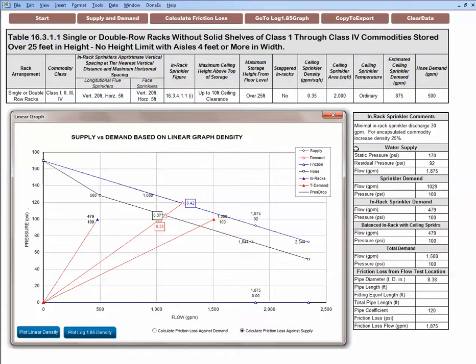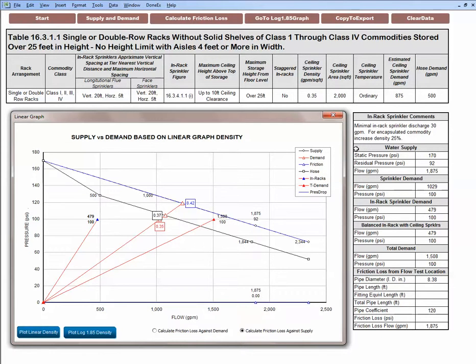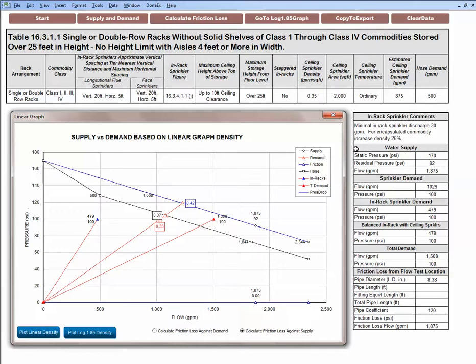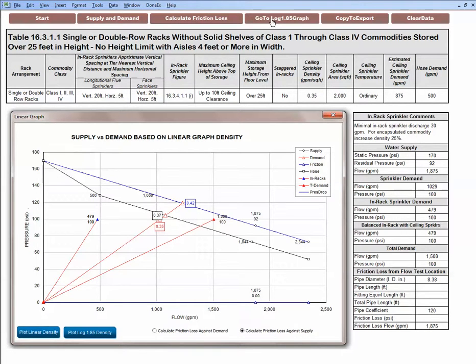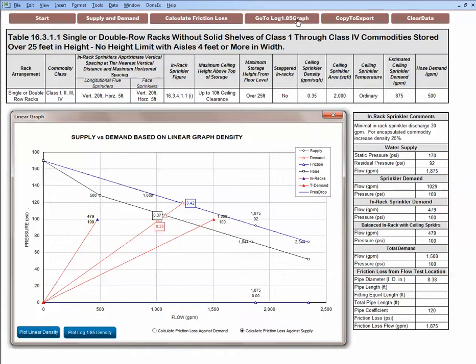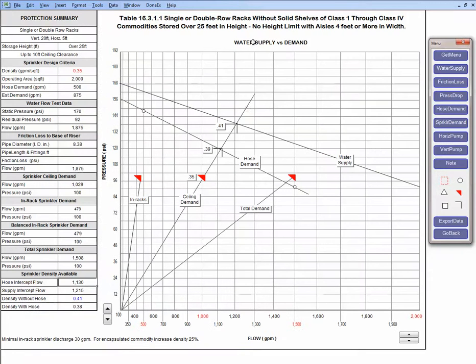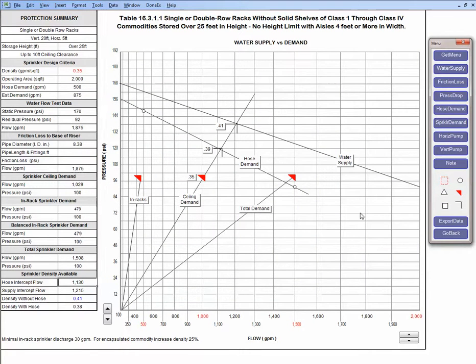And that's it, that's how quickly you could calculate articles of protection. It is an ideal tool for fire protection engineers that need to visit and evaluate protection in warehouses. The process is similar for other programs to evaluate flammable liquids, plastics, all kinds of occupancies and commodities found in NFPA 13. So I'm basically pulling information from NFPA 13 and NFPA 30 and other standards and use it to populate the fields. Then I enter water supply, sprinkler demand, friction loss and I could quickly generate this graph. This is a linear graph.